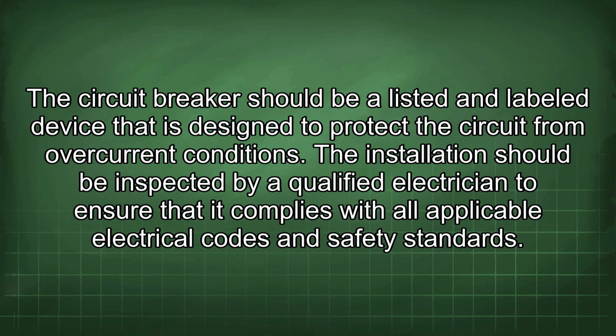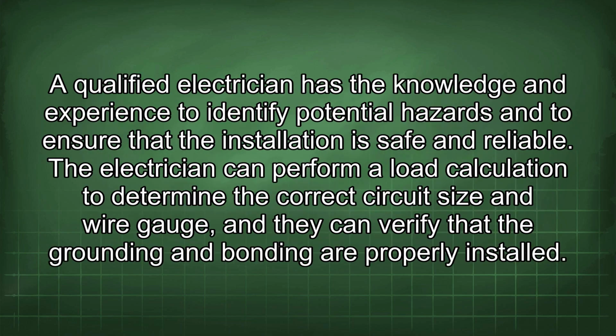conditions. The installation should be inspected by a qualified electrician to ensure that it complies with all applicable electrical codes and safety standards. A qualified electrician has the knowledge and experience to identify potential hazards and to ensure that the installation is safe and reliable. The electrician can perform a load calculation to determine the correct circuit size and wire gauge, and they can verify that the grounding and bonding are properly installed.